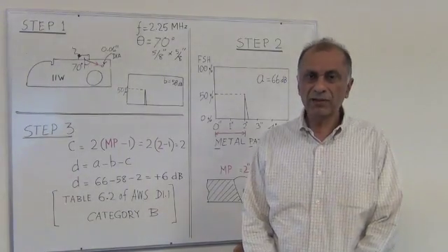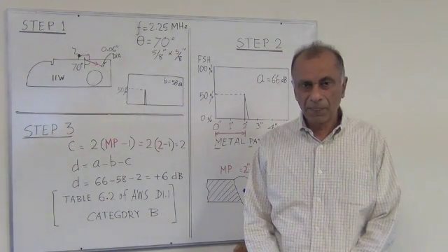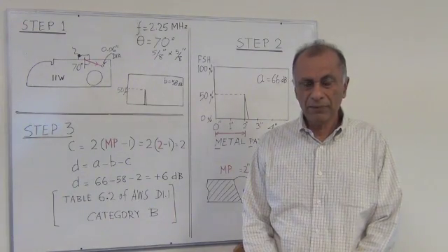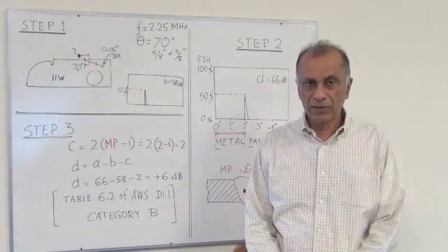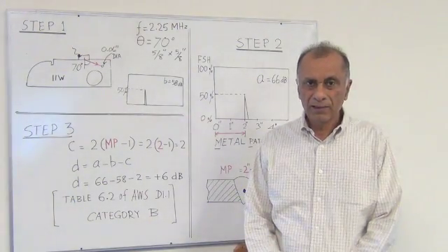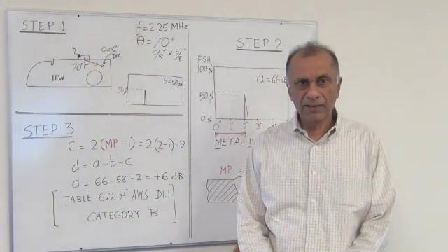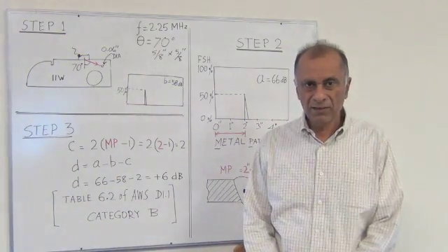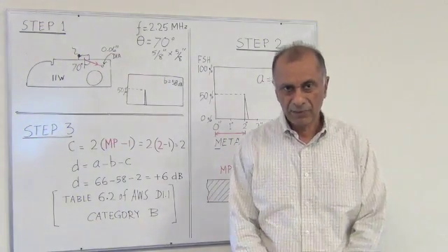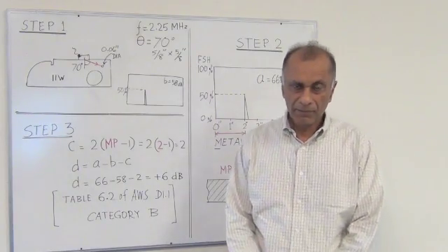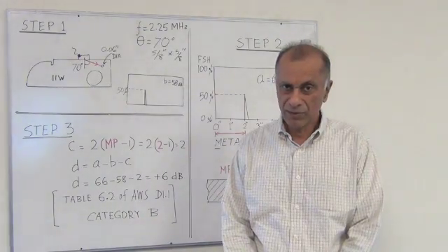We start the inspection. First, we have to get all the equipment. The pulse receiver for this inspection is the normal UT machine, and the second thing would be the ultrasonic probe. The probe requirement as per AWS D1.1 is a 2.25 MHz frequency probe, size 5/8 inch by 5/8 inch or slightly higher. But probes like 1/4 inch and 1/2 inch are not acceptable for this inspection.